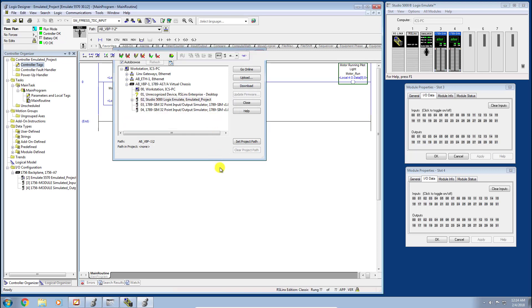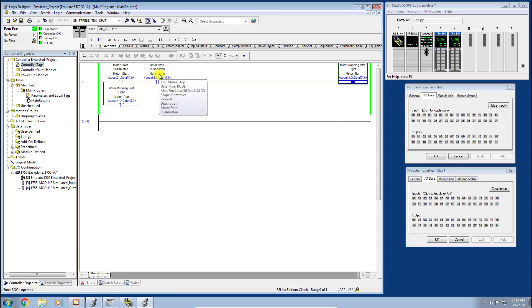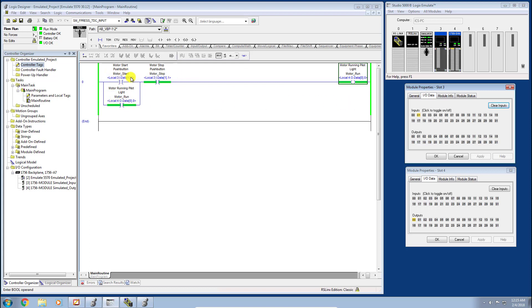Now that we've actually tied these tags to our simulated I/O and our emulated virtual backplane here, we can make use of the module property switches to actually toggle things on and off. Because this motor stop, usually your stop buttons are wired normally closed, which is why I'm using an XIC to monitor it, I'm going to go ahead and just flip that one on. You can see now if this was actually a normally closed stop pushbutton like is most common, we are monitoring the on state here. Perfect. I'm going to be an operator. I'm going to go ahead and push my pushbutton on, and notice now my output, my motor turns on and my output is sealing in that start button so we can release it.